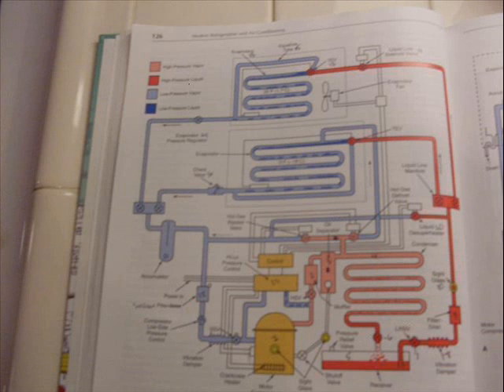Now, there is another part, not shown in the diagram, but you're welcome to use it. It's called a heat exchanger. You remember what the heat exchanger, where it's at? It takes the high-pressure liquid, and it wraps the liquid line around the suction line, and cools the high-pressure liquid to increase efficiency. Also, it would help evaporate any liquid droplets going back to the compressor.